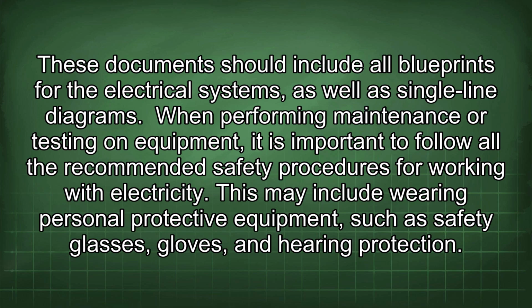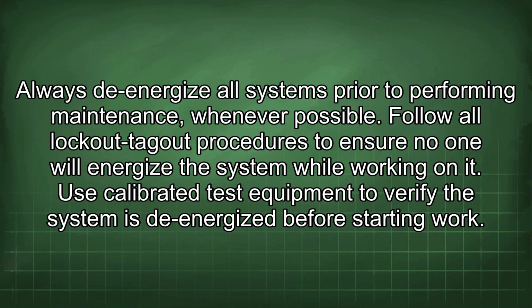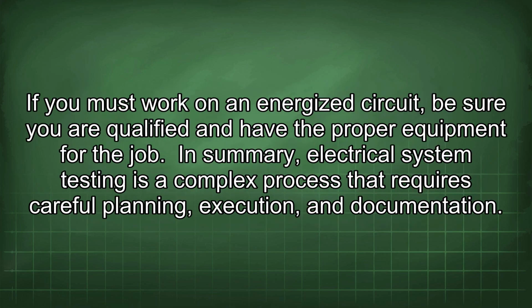When performing maintenance or testing on equipment, it is important to follow all the recommended safety procedures for working with electricity. This may include wearing personal protective equipment, such as safety glasses, gloves, and hearing protection. Always de-energize all systems prior to performing maintenance, whenever possible. Follow all lockout-tagout procedures to ensure no one will energize the system while working on it. Use calibrated test equipment to verify the system is de-energized before starting work. If you must work on an energized circuit, be sure you are qualified and have the proper equipment for the job.